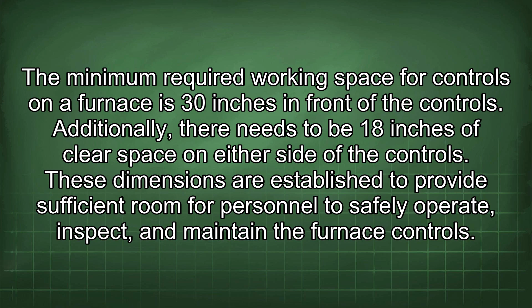The minimum required working space for controls on a furnace is 30 inches in front of the controls, with an additional 18 inches of clear space on either side. These dimensions provide sufficient room for personnel to safely operate, inspect, and maintain the furnace controls.